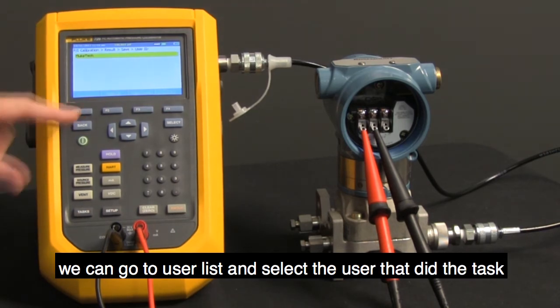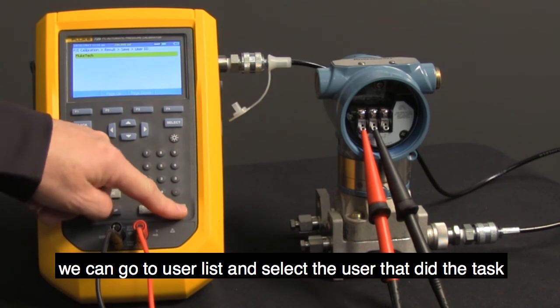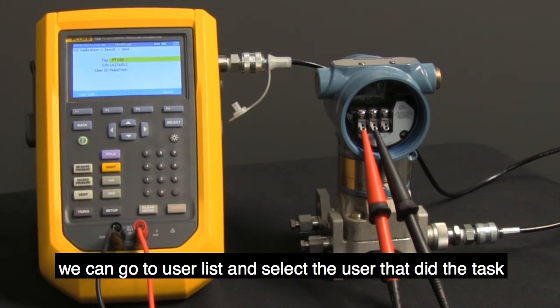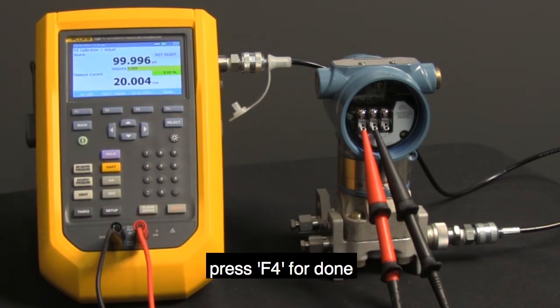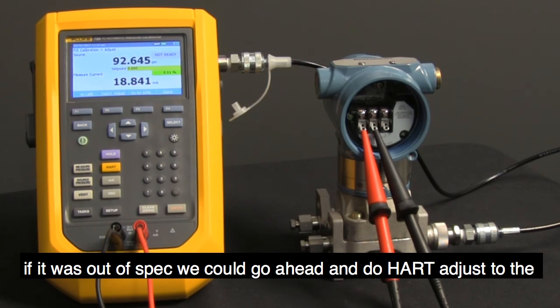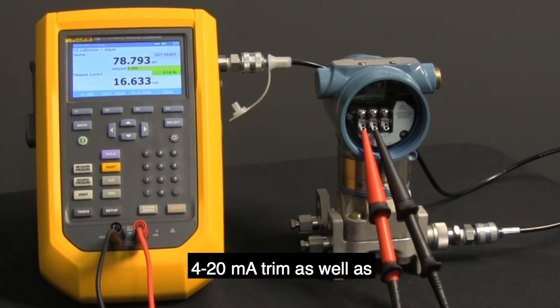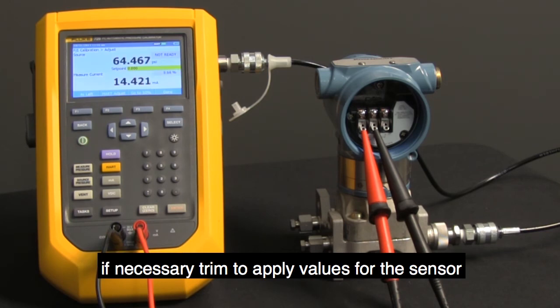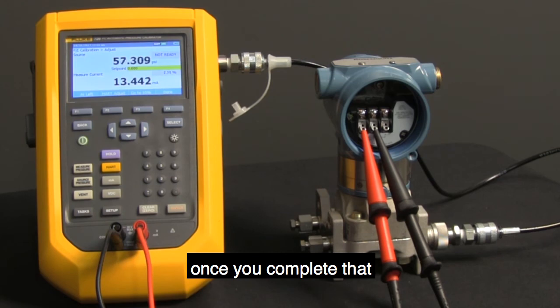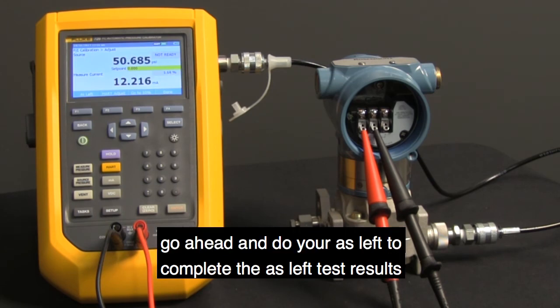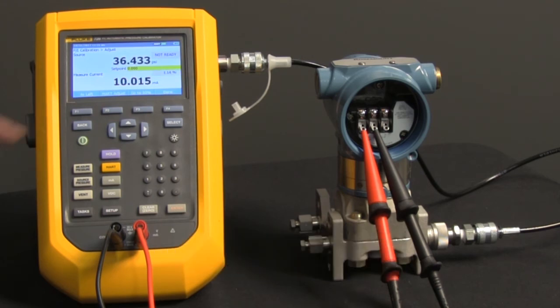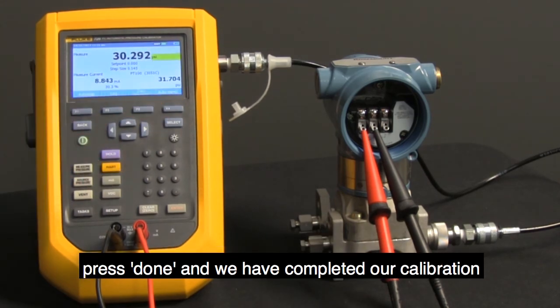We can go to user list and select the user that did the task. Press F4 for done. If it was out of spec, we could go ahead and do HART adjust to the 4-20 milliamp trim, as well as, if necessary, trim to applied values for the sensor. Once you complete that, go ahead and do your as left to complete the as found and as left test results. Press done, and we have completed our calibration.